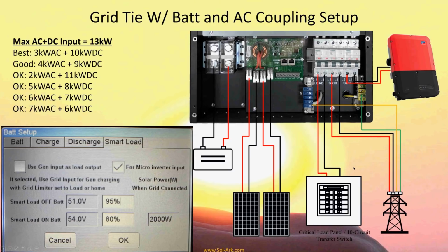Okay. Grid tie with battery and AC coupling. So here what we're doing is we want to use this generator port for something different now. We want to AC couple as well as DC couple. So we can take a string inverter and put it into the generator port, and we enable this microinverter input. And what we do is we program on. We want the system to come on at, let's say, 80% or below SOC values.